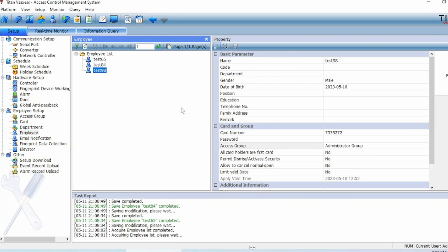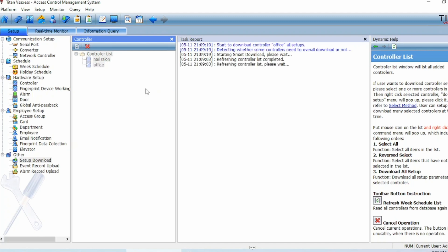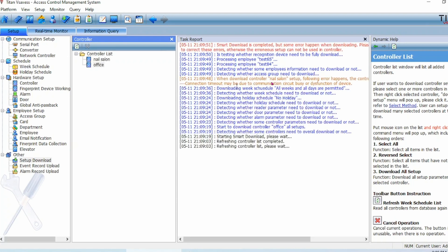Every time you make changes but forget to save, the software is smart enough to remind you. Once you're all set with the programming side, go down to Setup Download on the left-hand side, right-click on the new controller panel, and choose Start Smart Download. Because this is the first time we're downloading all the programs to the control panel, it takes a while. Here you can see I'm getting an error code for the nail salon — that's because the nail salon control panel is not connected to my network at this moment, and that's okay because we're only doing the office.